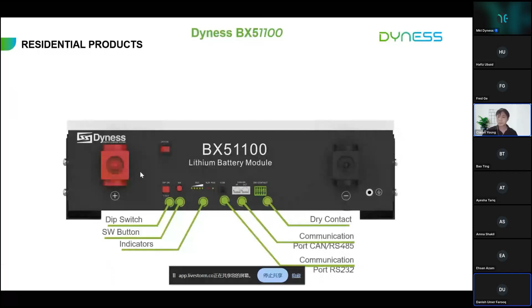As for the paralleling usage, here's the topological map. After paralleling the batteries, you have to connect the power cable and the DC breaker between batteries and inverters. As mentioned, our battery works in master-slave mode, and the whole storage system is controlled by master BMS. The first unit directly connected with the inverters will be the master battery, and this is the one where you connect the communication cable with the inverter. The other batteries are slave batteries, and their work status is controlled by the master BMS.